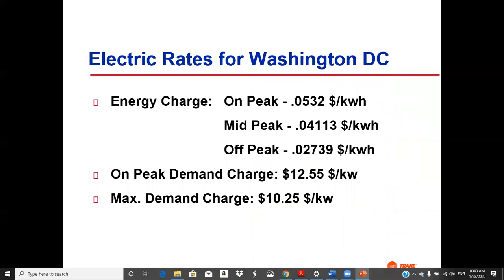Okay, so now on to the analysis. Basically what we're going to claim in this analysis is that we're going to avoid the demand charge with the absorber, because it can cool all day long, but it doesn't hardly have any electrical demand. So the electrical demand is going down, and we're going to buy natural gas to make our chilled water during the on-peak periods. Off-peak, we go ahead and run the centrifugal.